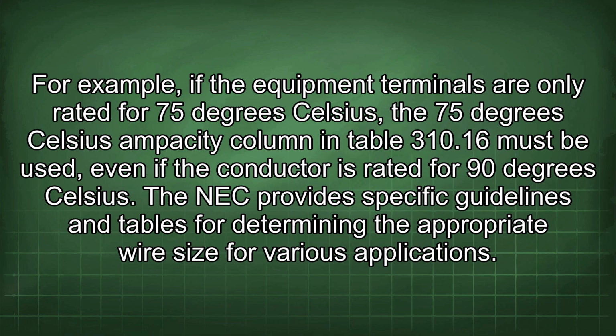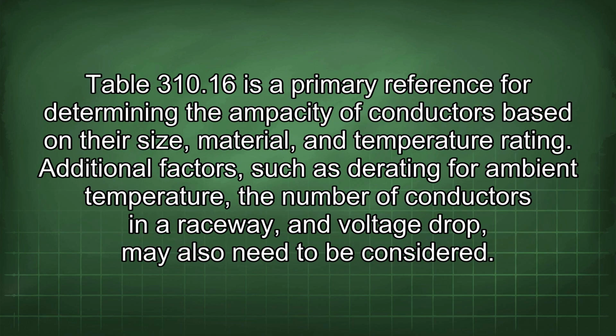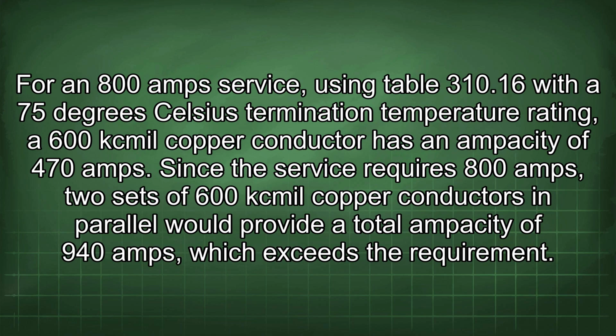The NEC provides specific guidelines and tables for determining the appropriate wire size for various applications. Table 310.16 is a primary reference for determining the ampacity of conductors based on their size, material, and temperature rating. Additional factors such as derating for ambient temperature, the number of conductors in a raceway, and voltage drop may also need to be considered. For an 800 amp service, using Table 310.16 with a 75 degrees Celsius termination temperature rating, a 600 kcmil copper conductor has an ampacity of 470 amps. Since this service requires 800 amps, two sets of 600 kcmil copper conductors in parallel would provide a total ampacity of 940 amps, which exceeds the requirement.